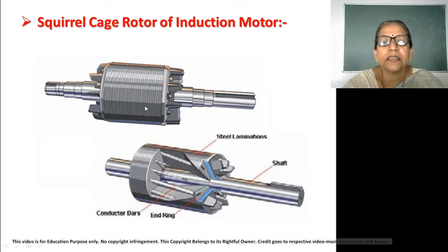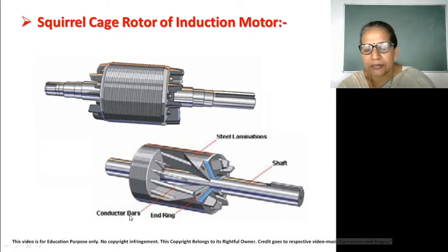So just like the stator core, the rotor core is also laminated and it is mounted on this shaft. When the slots are provided, they are slightly tilted, and this is for the purpose of avoiding interlocking of stator poles and rotor poles and to reduce the humming noise. Other parts are as usual. It will also have end rings, bearings, etc.